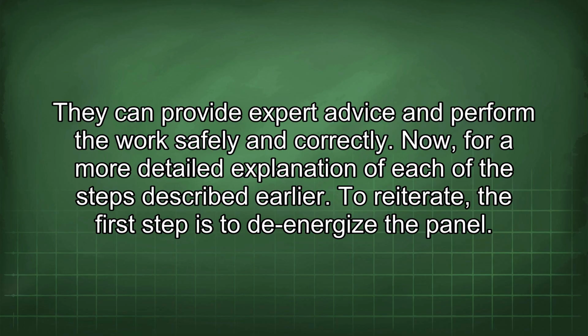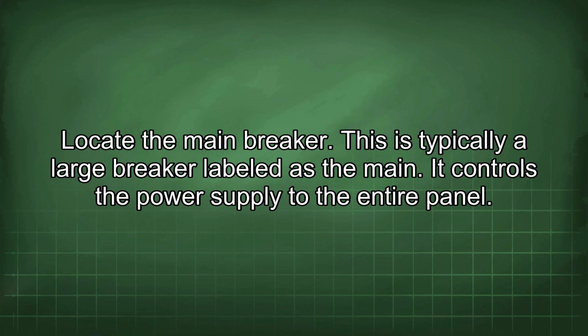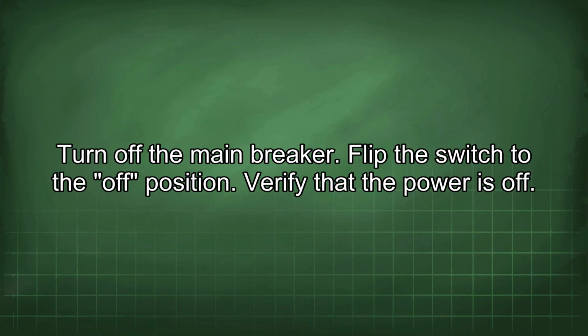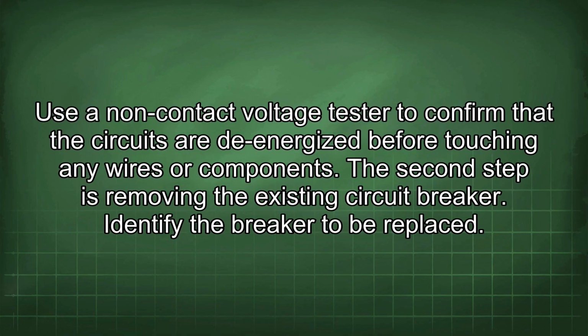Now, for a more detailed explanation of each of the steps described earlier. To reiterate, the first step is to de-energize the panel. Locate the main breaker. This is typically a large breaker labeled as the main. It controls the power supply to the entire panel. Turn off the main breaker. Flip the switch to the off position. Verify that the power is off. Use a non-contact voltage tester to confirm that the circuits are de-energized before touching any wires or components.